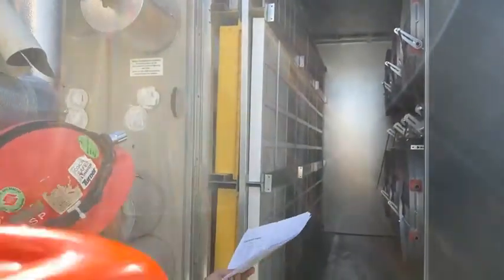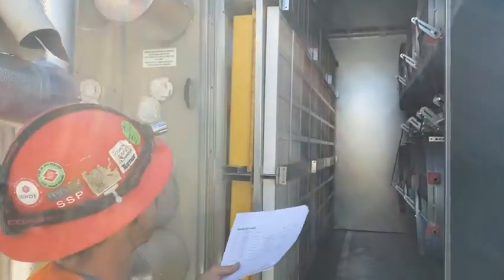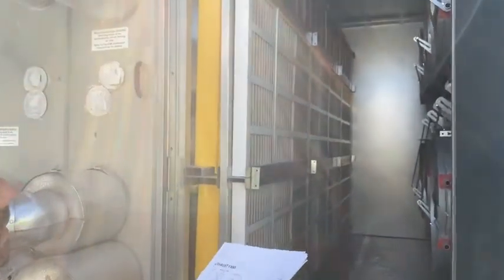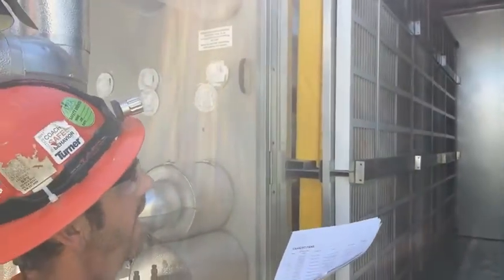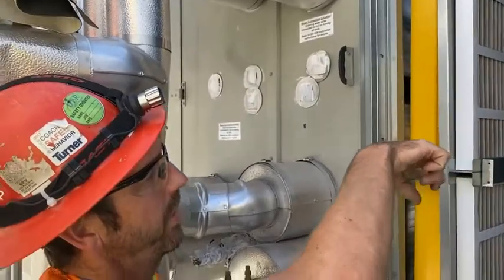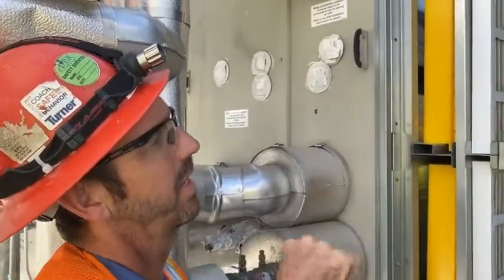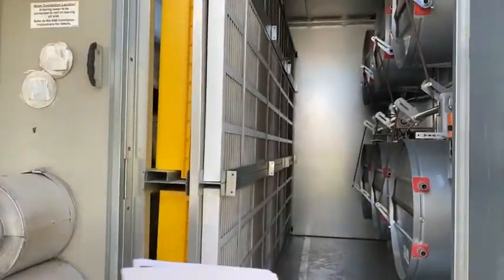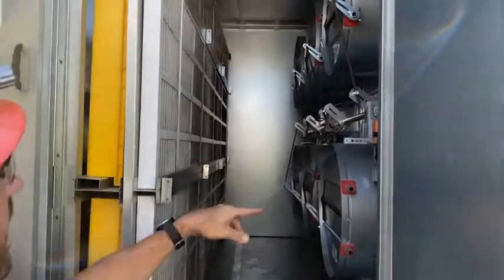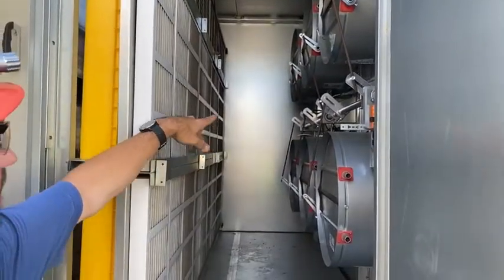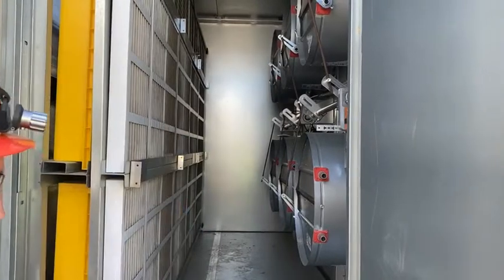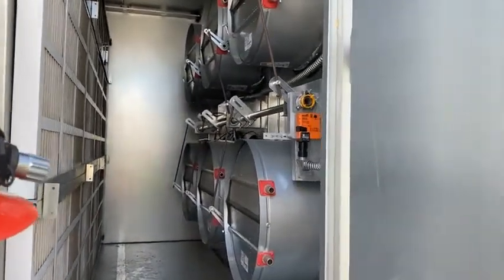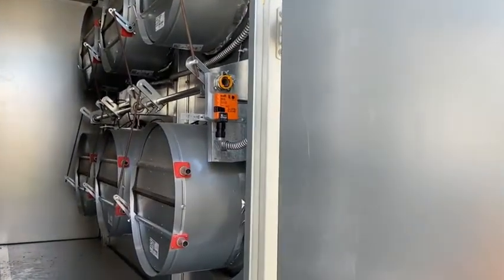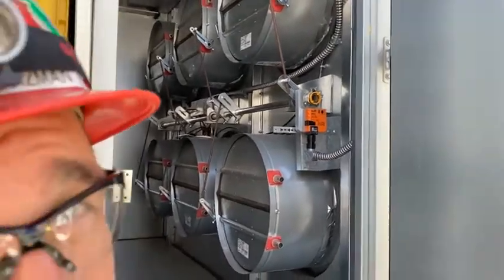So we have 6 outside air canisters that are drawing the air in from the outside. On each one of the inlet cones, there's flow sensing devices. The flow sensor devices report back to a control board up in the middle. So the outside air is controlled also? Well, controlled, it's more just reading the CFM, okay?